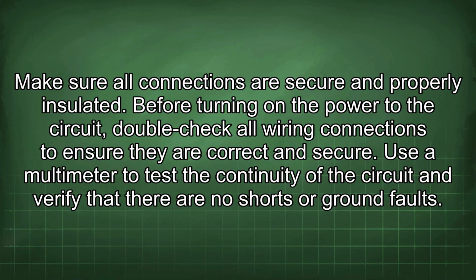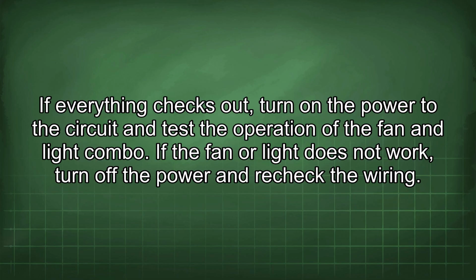Before turning on the power to the circuit, double-check all wiring connections to ensure they are correct and secure. Use a multimeter to test the continuity of the circuit and verify that there are no shorts or ground faults. If everything checks out, turn on the power to the circuit and test the operation of the fan and light combo. If the fan or light does not work, turn off the power and recheck the wiring.